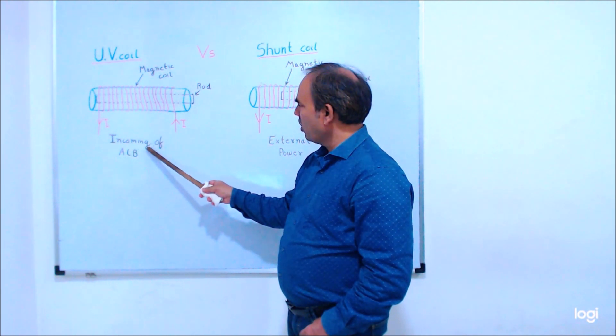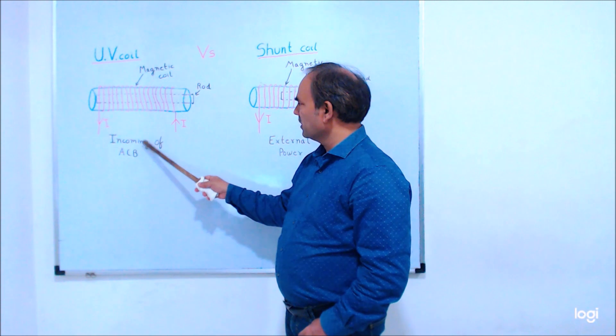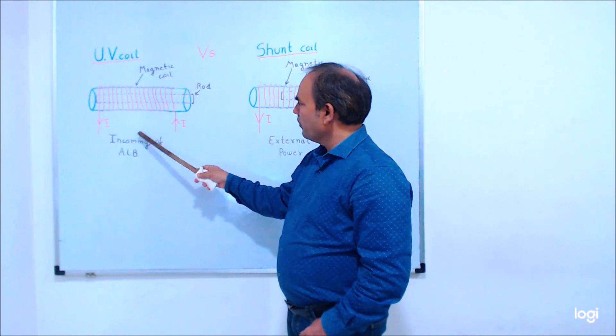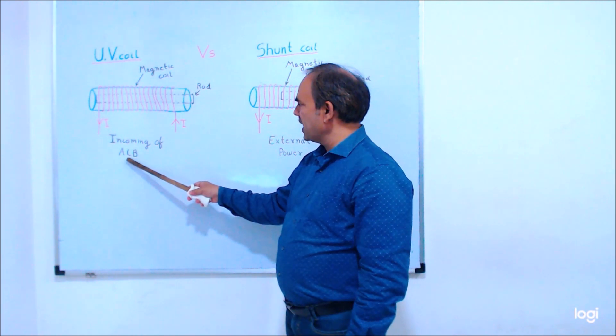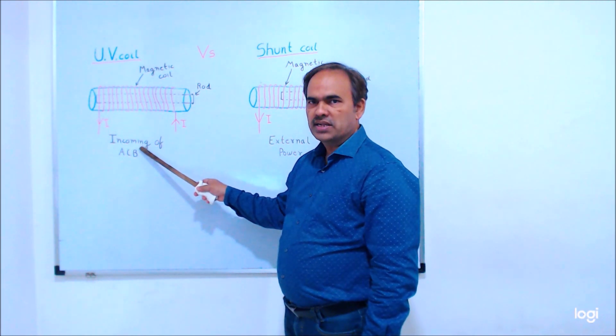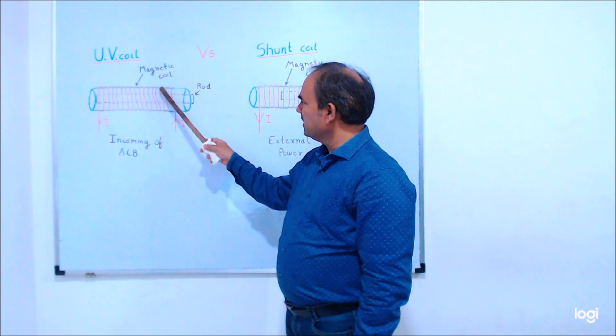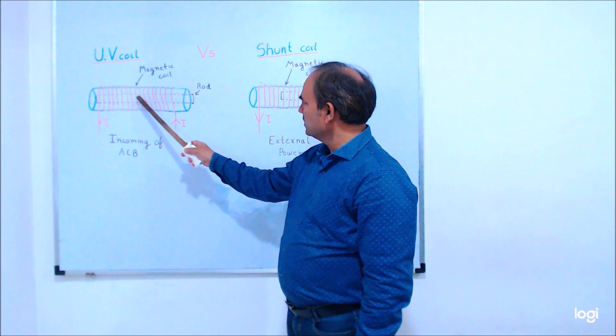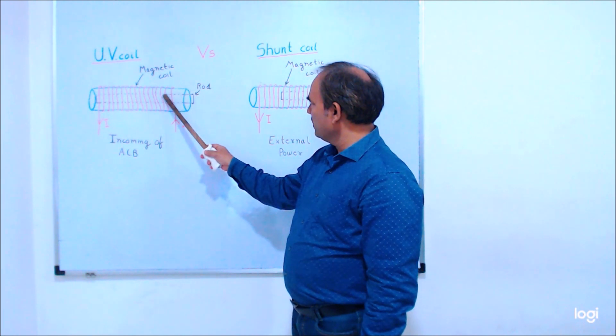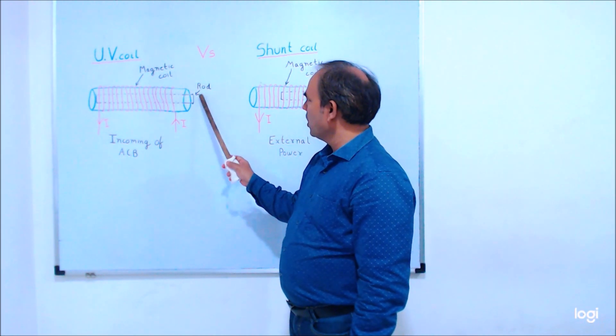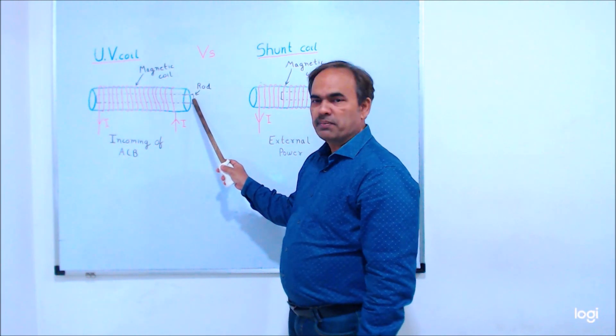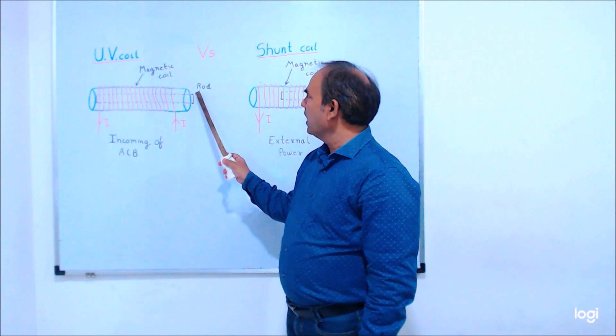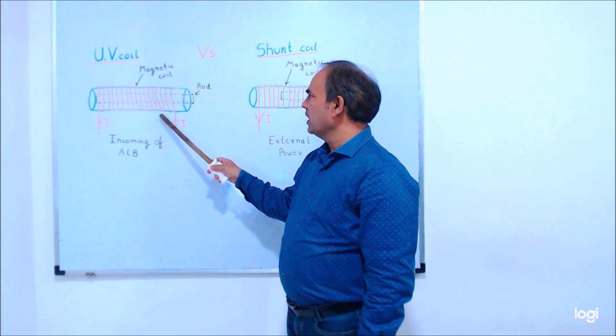This magnetic coil gets power from the incoming supply of the air circuit breaker, so it is always in an energized condition. Whenever the incoming supply of the air circuit breaker fails, it gets de-energized, and this piston will come outwards and push or hit the tripping mechanism of the air circuit breaker, causing it to trip.